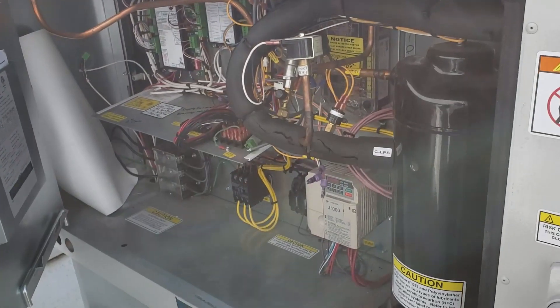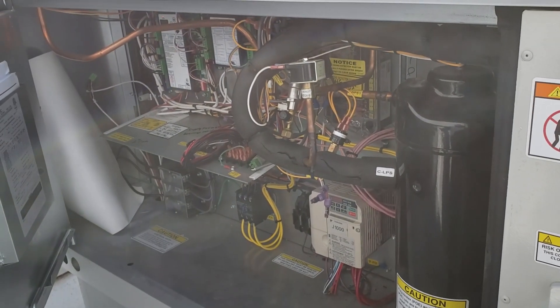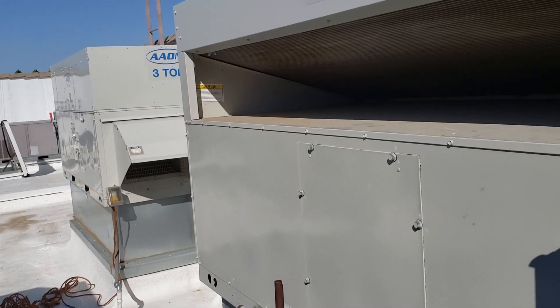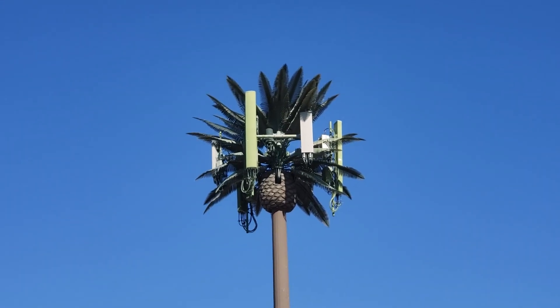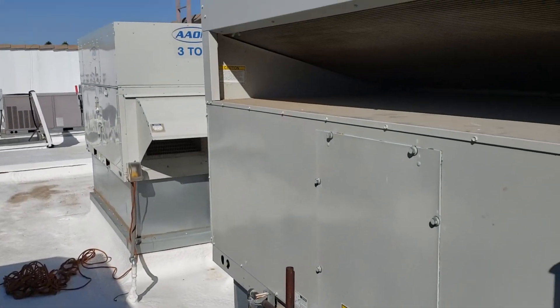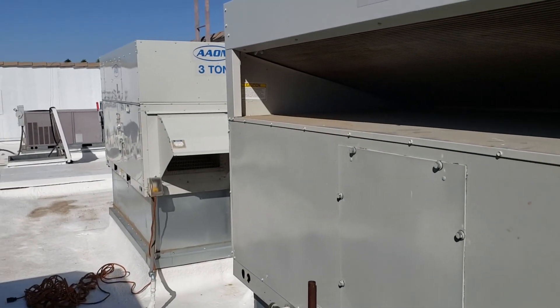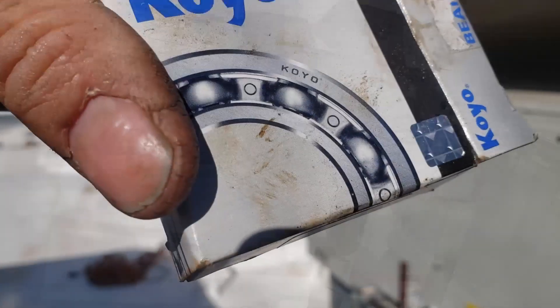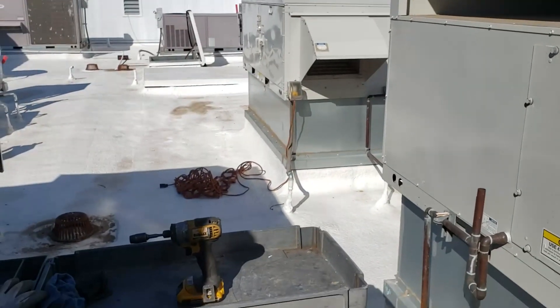Out of the AAON units installed in the last four or five years, I've had to replace bearings quite a few of them. I figure if anything, these Koyo or whatever brand aftermarket bearings will probably be better than what came in those Baldor motors to begin with.